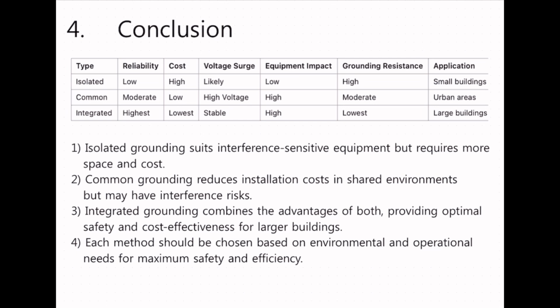Conclusion. Comparison of grounding types. Summary. Isolated grounding is well suited for protecting equipment highly sensitive to electromagnetic interference, but requires more installation space and higher costs. Common grounding is economical with lower installation and maintenance costs, though it may pose some risk of interference. Integrated grounding combines the benefits of both systems, providing optimal safety and cost-effectiveness, especially for large buildings.